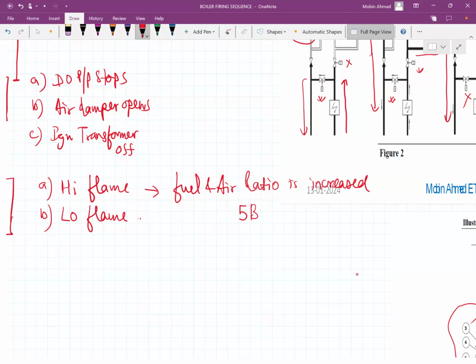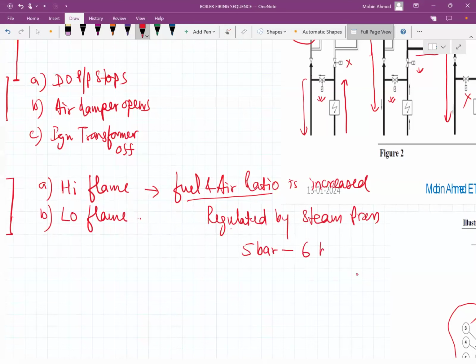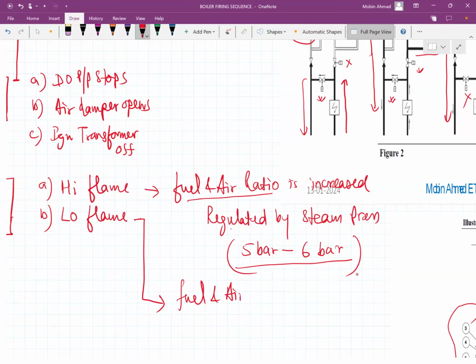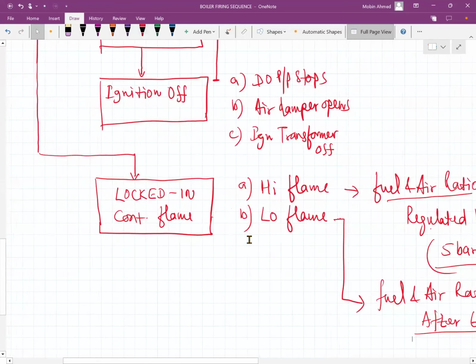After the starting, it is again regulated by the steam pressure. Between 5 bar and 6 bar, there will be high flame. I am giving this just to make you understand how it is happening. After 6 bar, the fuel and air ratio will decrease. So it will continue firing in the low flame. So this will be the locked in period.